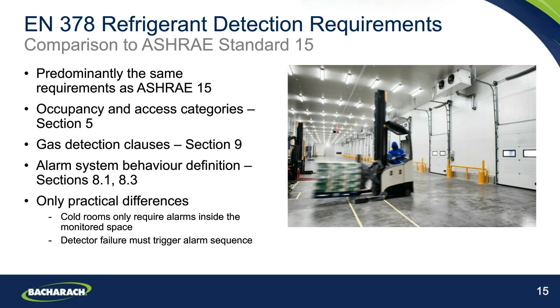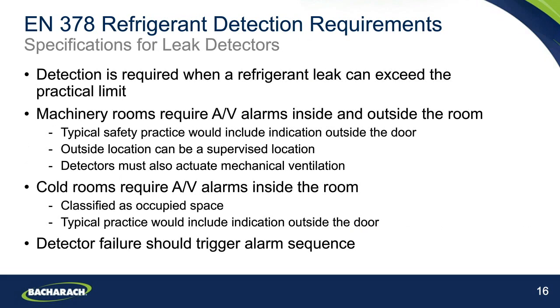So if we were to summarize the EN 378 refrigerant detection requirements, detection again is required when a refrigerant leak can exceed the practical limit. Machinery rooms again require audio and visual alarms both inside and outside of the room. It's not quite as explicit as ASHRAE 15, but we would see typical safety practice to include an indication outside the entrance to the door, but that outside location could technically be in a supervised location also. And the code also determines that detectors must actuate mechanical ventilation.